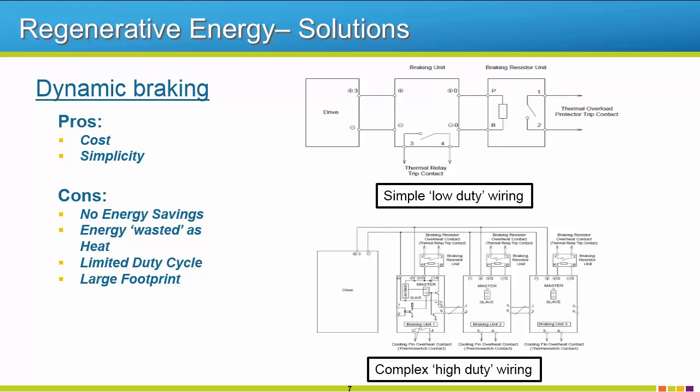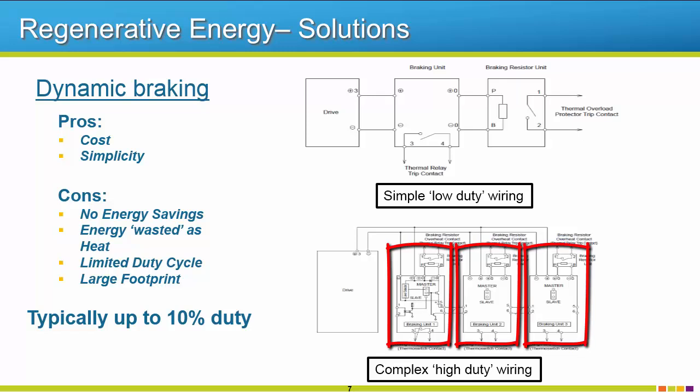Additionally, when an application calls for a higher duty cycle due to increased regen, the size of the braking transistor and resistor will get larger and could multiply. Braking modules are run in parallel. This results in a larger footprint and more wiring. Dynamic braking is most commonly used on applications requiring a duty cycle of 10% or less, but it is not limited to that number.